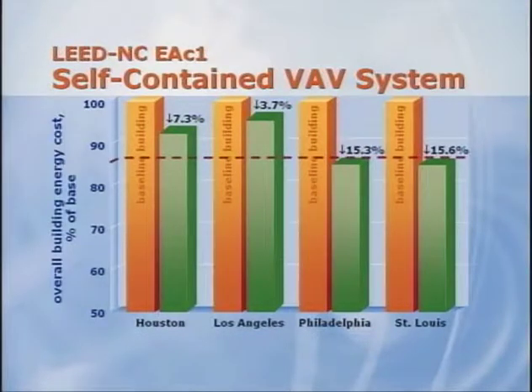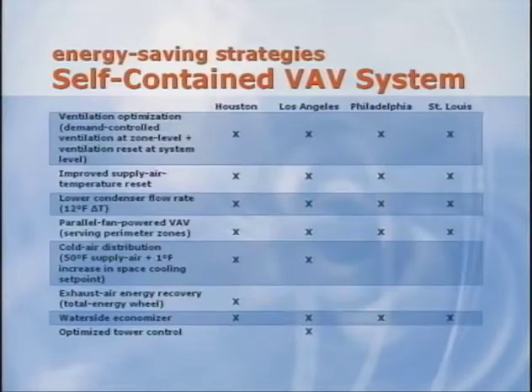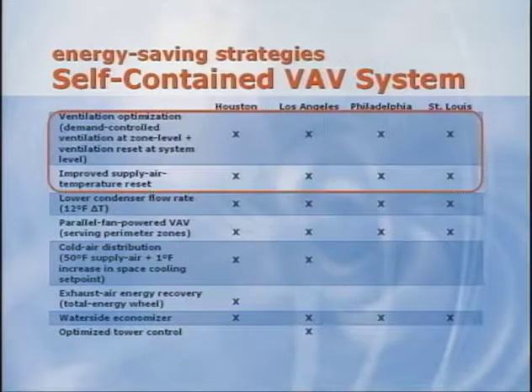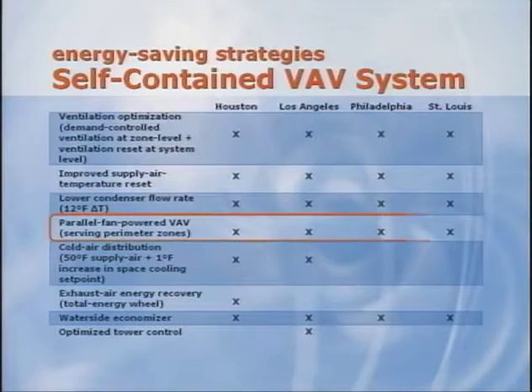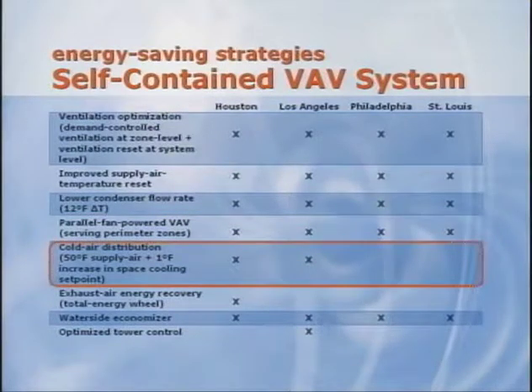The proposed building achieved 7% energy cost savings in Houston, about 4% in Los Angeles, 15% in Philadelphia, and about 16% in St. Louis. Since the air side of this system is very similar to rooftop VAV, several of the energy saving strategies are the same. Like before, the ventilation optimization and improved supply air temperature reset control sequences were used in all 4 locations, and parallel fan-powered VAV terminals were used for the perimeter zones. For both Houston and Los Angeles, the system was designed for cold air distribution, 50-degree supply air in this case.